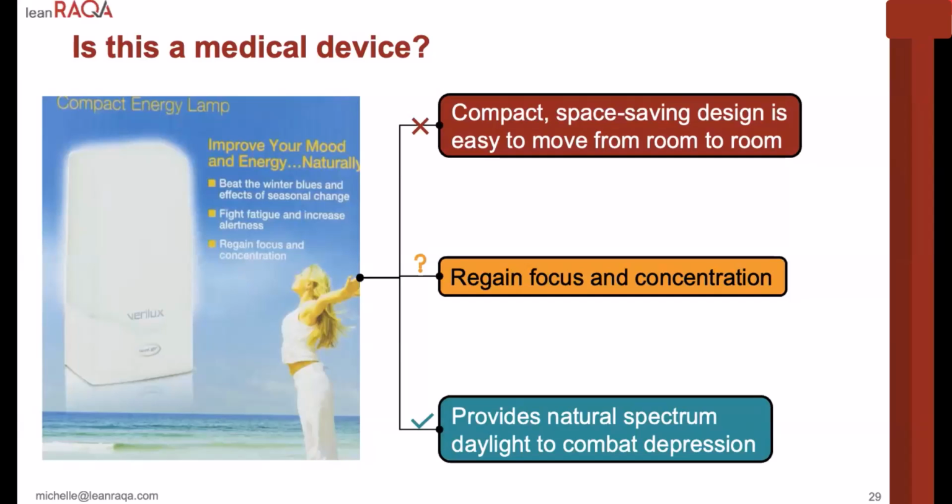It used to be insomnia, anxiety, and depression in the regulatory indications, and they split them apart, and they made depression a class 3 PMA for the exact same technology, exact same type of device, but the indication of depression became a class 3 and the other two became a class 2.